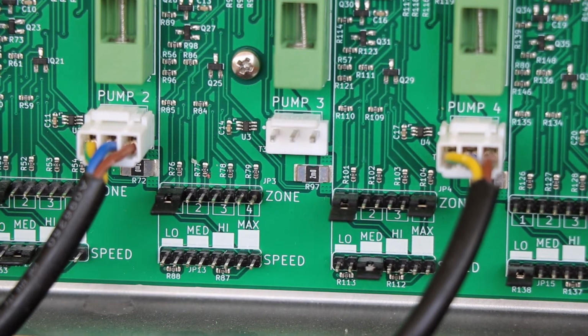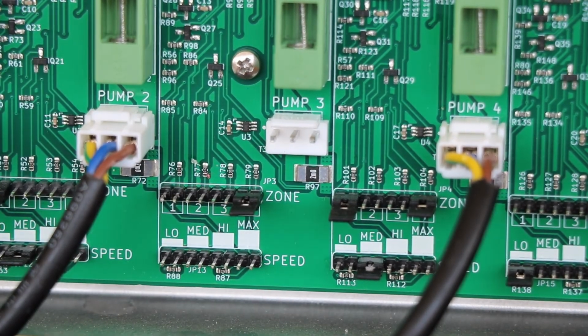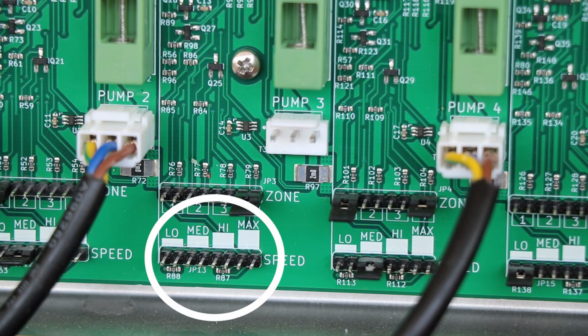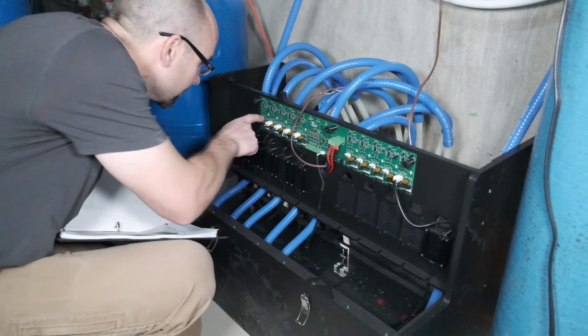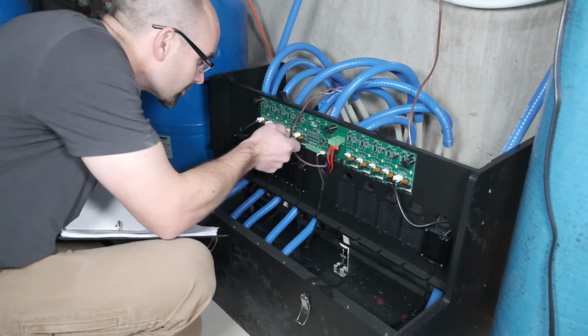The other pumps may be assigned to specific zones by moving the jumper to the pins labeled with that zone number. Now, we're going to assign pump speeds. Just below the zone selection is the speed selection for the pump. Assign speeds by moving a jumper to the matching pins. Set pumps as low as possible to keep your house warm.